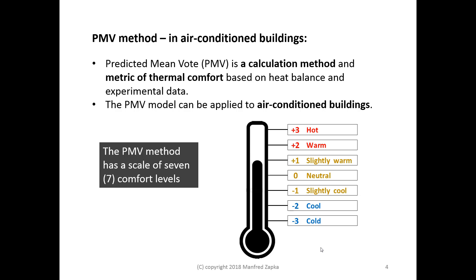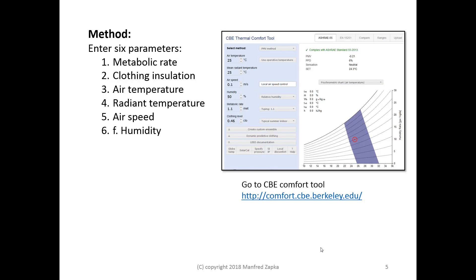Since PMV is a calculation method, we can calculate specific values. We use 6 parameters: metabolic rate, clothing insulation, air temperature, mean radiant temperature, air speed, and humidity.